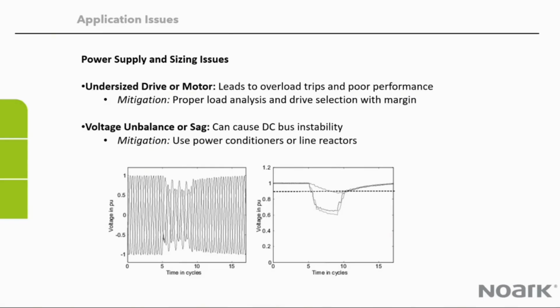And then you could run into power supply and sizing issues. If your drive and motor are undersized for the application that you're using it on, you could end up with nuisance trips or irregular performance. You'll want to review that and determine what the appropriate size motor or drive is, and allow for a reasonable tolerance above that to maintain the lifespan of the motor or the drive. And then voltage unbalance and sag, which could affect the stability of the DC bus. Power conditioners or line reactors will help mitigate much of that.